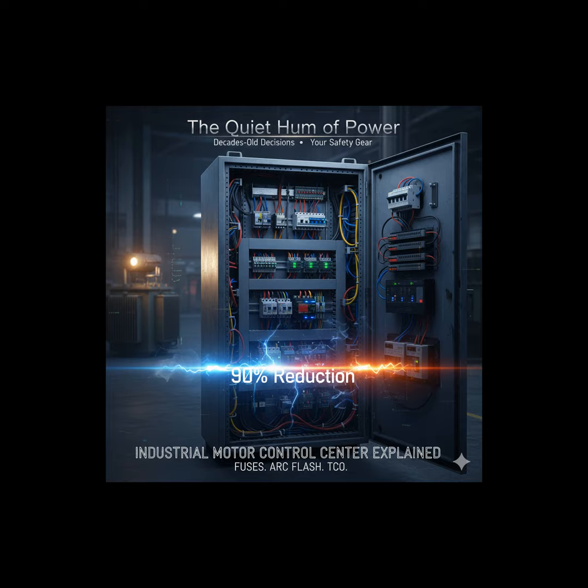Okay, moving beyond just turning on and protecting the motor, modern MCCs are central hubs for advanced motor management. If a motor needs to start smoothly or change speed continuously, we're looking towards sophisticated drives. What's the defining difference between a soft starter and a variable frequency drive? They solve two different problems. Soft starters, using SCR or thyristor technology, are designed purely for the startup phase. They slowly ramp up the voltage supplied to the motor over a controlled time, say 5 to 10 seconds. So it's a gentle start. A very gentle start. It minimizes the massive inrush current and the torque stress that happens with a direct online start. Once it's ramped up, the motor runs at a fixed constant speed.